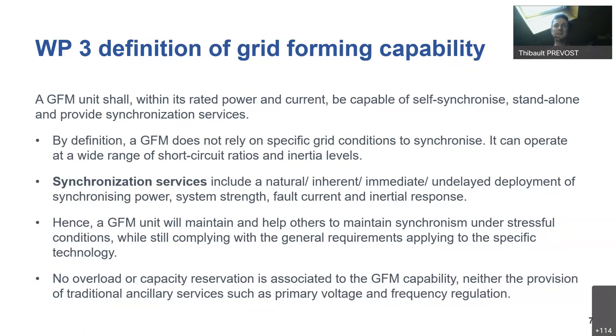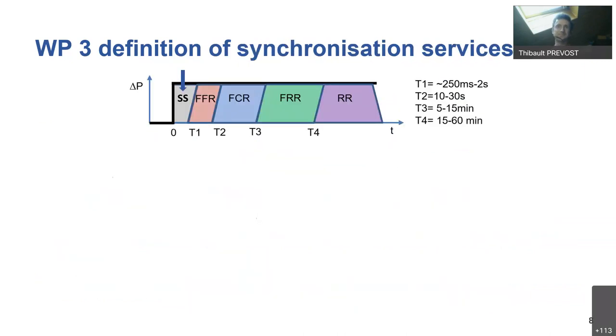So these units will maintain, but also help other units to maintain, synchronism on the grid. And again, we don't want any oversizing or capacity reservation to be able to provide this grid forming. We want to make best use of what's already available, to reduce the cost and to ensure that a lot of units will be able to provide such capability.